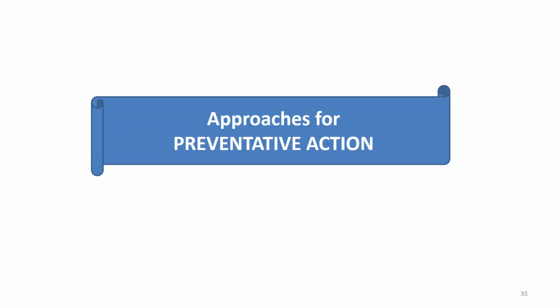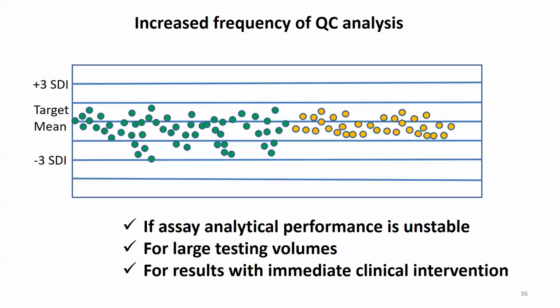One common type of preventative action is a more robust or frequent preventative maintenance program. The next couple of slides show some additional types of approaches for effective preventative actions. A common preventative action to prevent reporting of erroneous results is to increase the frequency of QC analysis. The regulatory minimum is 2 levels of QC analyzed per 24 hours of patient testing, but many laboratories choose to analyze QC more frequently, like once per shift or even once per every few hours.